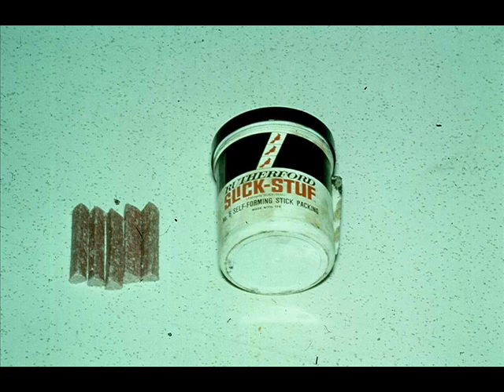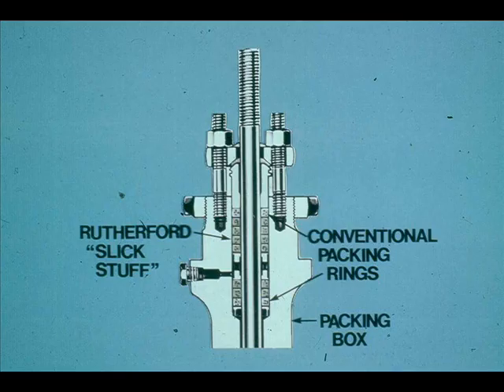Lubricants and packing other than those of a specific valve manufacturer can be used. Rutherford Slick Stuff is currently being used at Baytown and Baton Rouge plants. This packing is a Teflon base, self-forming material that can withstand 600 degrees Fahrenheit temperature. A conventional Teflon graphite packing ring is used for the first and last rounds of packing when you pack a control valve with Slick Stuff. Rutherford Slick Stuff requires no lubrication, but Rutherford No. 4 Lubricant is an excellent packing lubricant and will prolong the life of any packing.